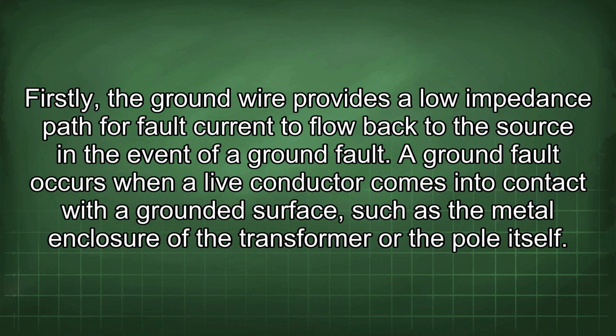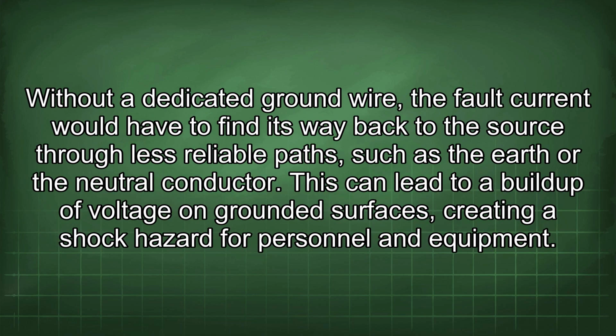A ground fault occurs when a live conductor comes into contact with a grounded surface, such as the metal enclosure of the transformer or the pole itself. Without a dedicated ground wire, the fault current would have to find its way back to the source through less reliable paths, such as the earth or the neutral conductor. This can lead to a build-up of voltage on grounded surfaces, creating a shock hazard for personnel and equipment.